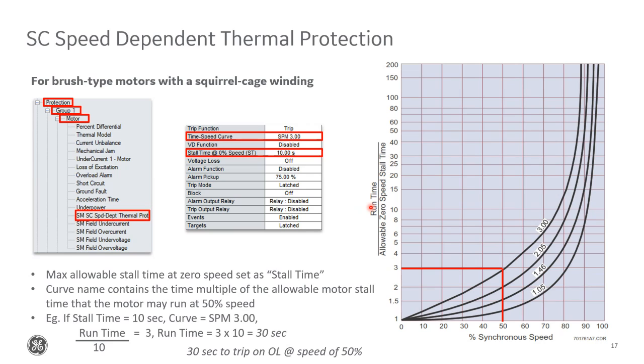So what that means is if our motor data sheet indicates an allowable stall time of 10 seconds, then we program this stall time setting as 10 seconds. Then we choose a curve number based on how long our data sheet shows it should take the motor to accelerate to 50% speed. The curve names here are actually a multiple of the motor stall time at 50% speed. So at this point here, if we draw a line at 50%, you can see curve three is at a multiple of 3. Curve 2 at 50% is at a multiple of about 2, and so on for the other two.